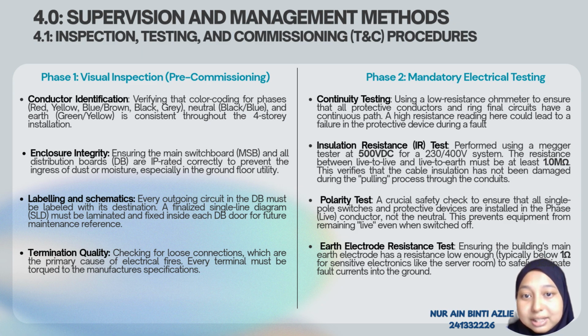Next, insulation resistance (IR) testing. Performed using a megger tester at 500 volts DC for a 230 or 400 volt system. The resistance between live to live and live to earth must be at least 1 megaohm. This verifies that the cable insulation has not been damaged during the pulling process through the conduits. Next is the polarity test, a crucial safety check to ensure that all single pole switches and protective devices are installed in the phase conductor, not the neutral. This prevents equipment from remaining live even when switched off.